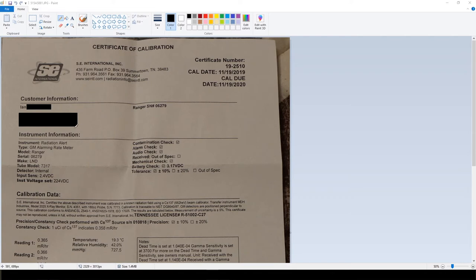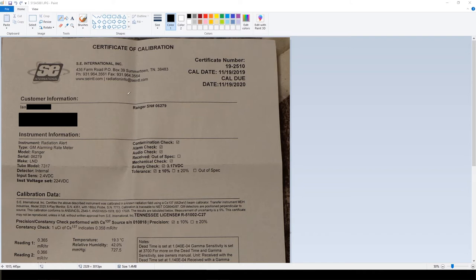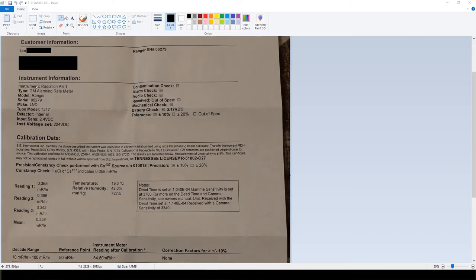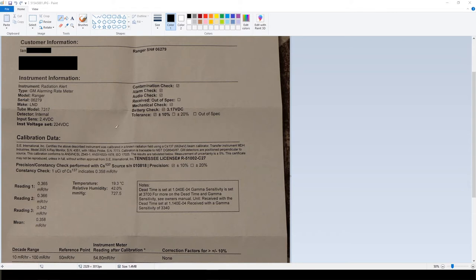You can see where it got calibrated, the date it got calibrated, and then the due date for it to be done next year. Then some instrument information: my model Ranger, my serial number, the type of tube I have, the model number 7317, and some other cool stuff like they did a battery check, tolerances, and stuff like that.